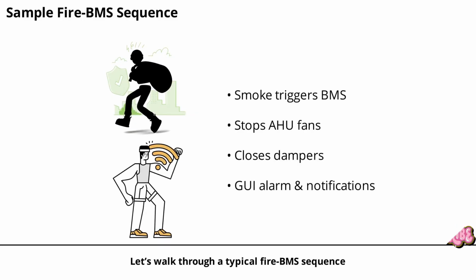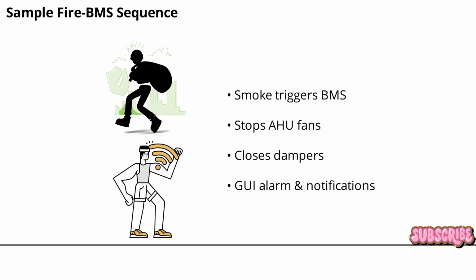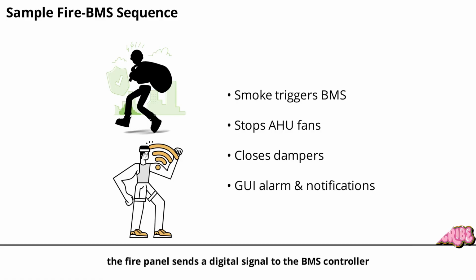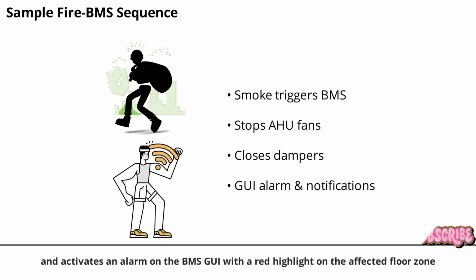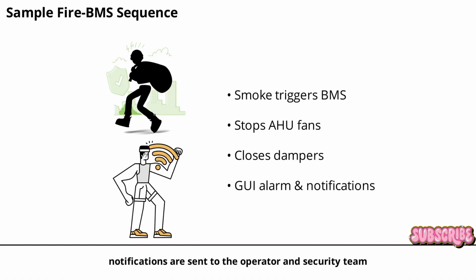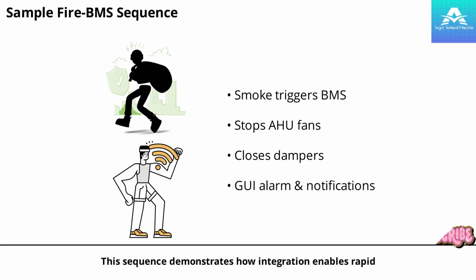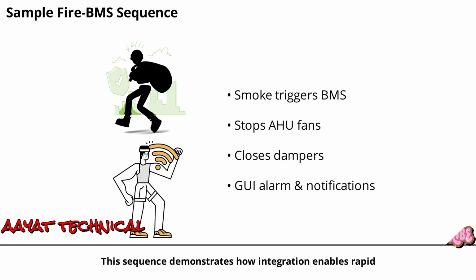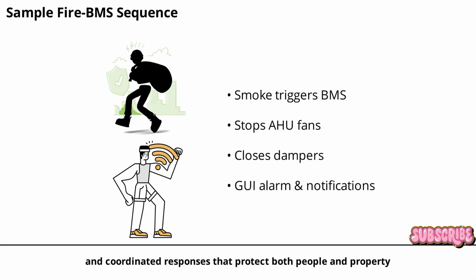Let's walk through a typical fire BMS sequence, such as an AHU shutdown triggered by smoke detection. First, the fire panel sends a digital signal to the BMS controller. The BMS then stops the AHU supply and return fans, closes the return air and fresh air dampers, and activates an alarm on the BMS GUI with a red highlight on the affected floor zone. Finally, notifications are sent to the operator and security team. This sequence demonstrates how integration enables rapid, automated, and coordinated responses that protect both people and property.